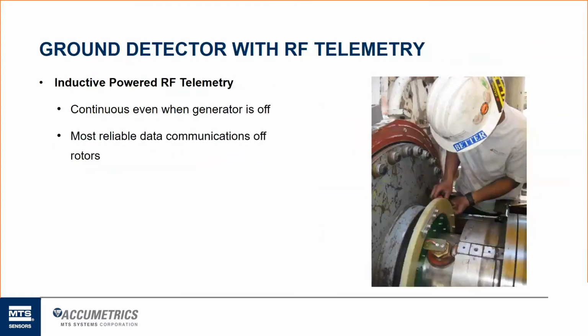So the next style is ours, ground fault detection using radio frequency telemetry. Ours is induction powered. What that means is we're bringing the necessary power across the wireless air gap out to the rotor mounted transmitter that powers our electronics out on the transmitter. And in turn, it sends a data signal across that air gap back to the stationary side to let us know what the field voltage is and the field resistance out on the generator.